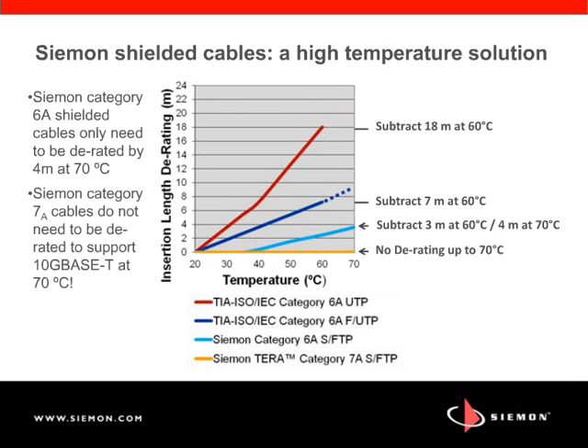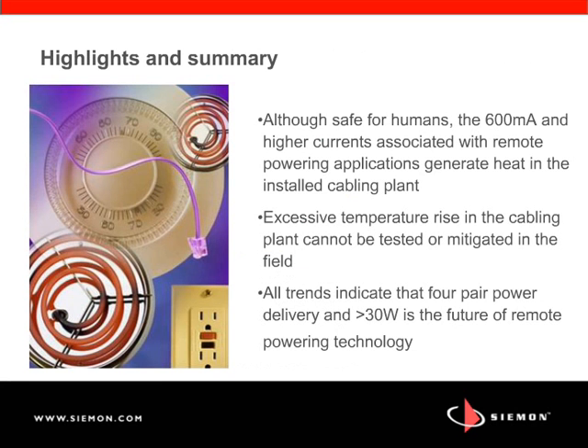We've talked about mechanical and electrical implications of remote powering. So again, I want to emphasize the types of current levels associated with remote powering are very safe. They're not going to damage humans. They fall under the safety extra low voltage category, but they do have implications, and those implications affect cabling selection. The implications are temperature rise in bundles and potential for arcing when unmating under load. All trends indicate that we're migrating from 2-pair to 4-pair power delivery, and clearly greater than 30-watt capability is the future of remote powering technology.